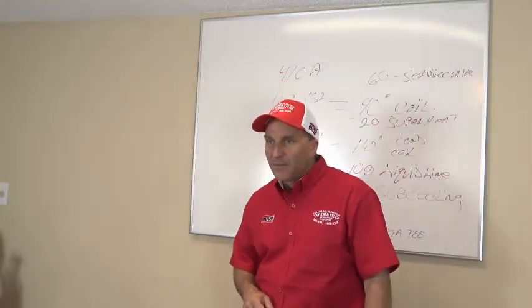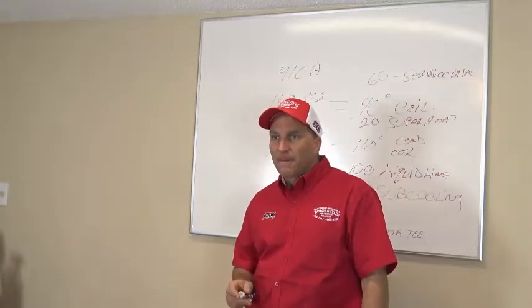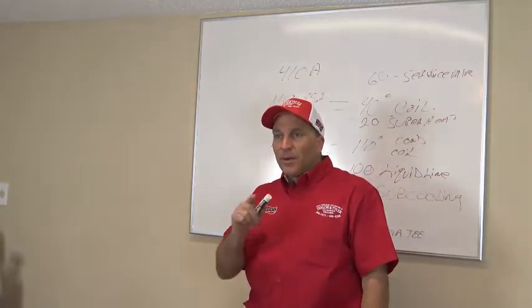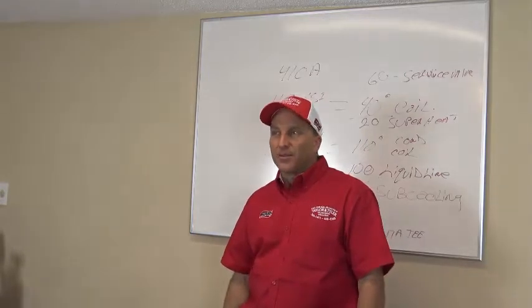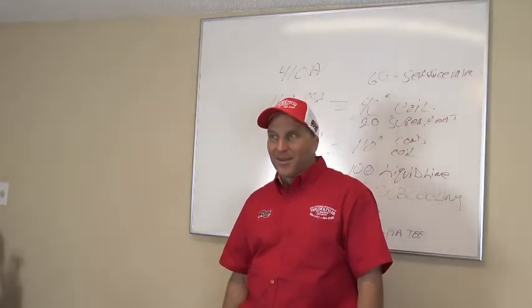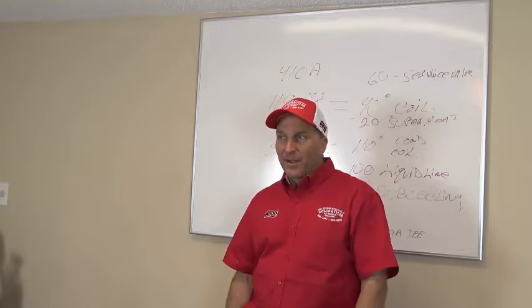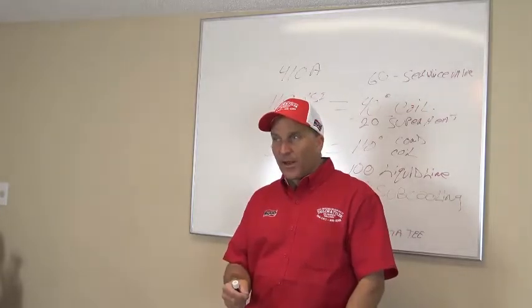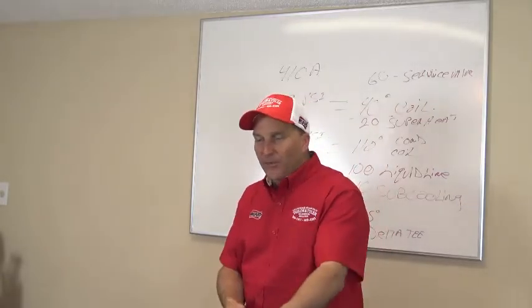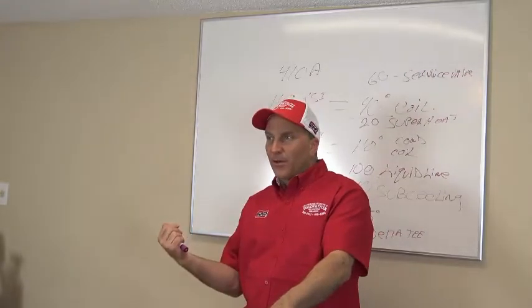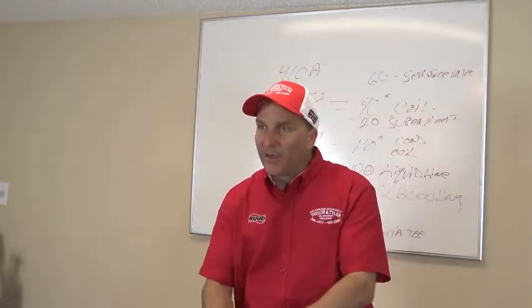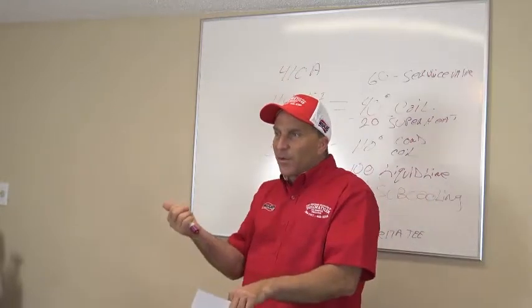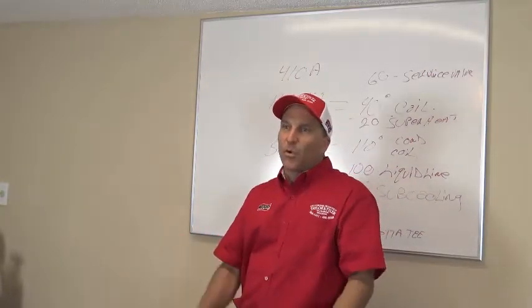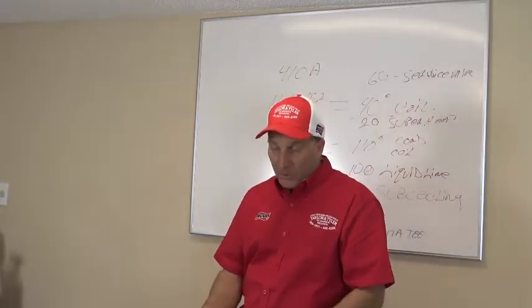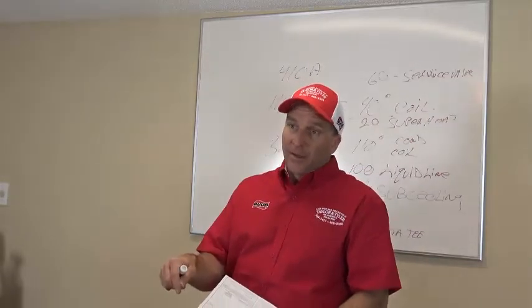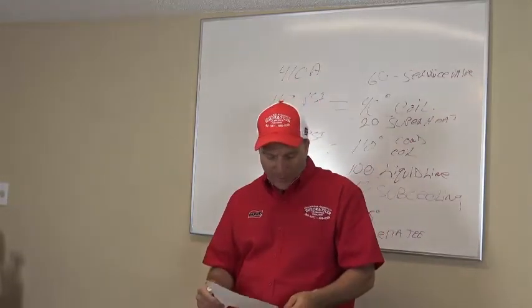Yeah. How? Well, you can pump down the unit. Now, you pump down the system to about 5 pounds of pressure inside the system. Now that you got it down to about 5 pounds of pressure, you get your other Schrader pin ready. You pull that one out, put your finger over it because the pressure is going to push out. Then you take your other pin, put it in there and screw it in there. And because the pressure is blowing out and not sucking in, you're not getting moisture in the line. Right. Okay? So it's possible to change a Schrader pin without having the Schrader valve remover tool. Okay?